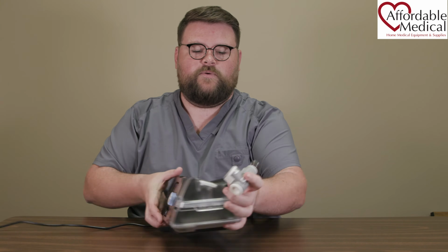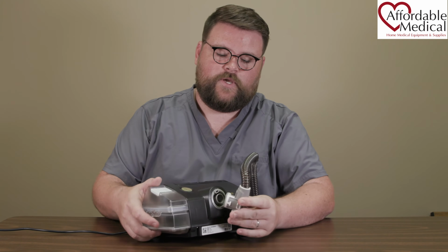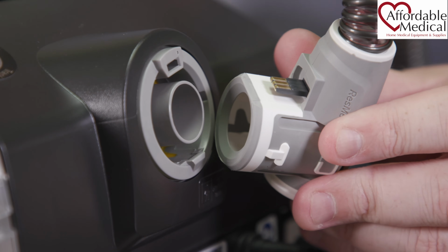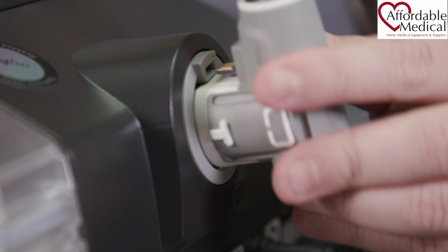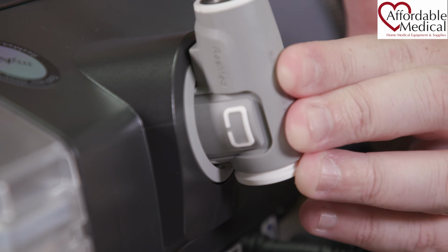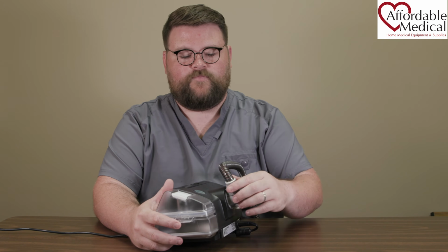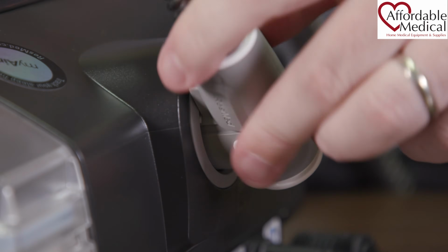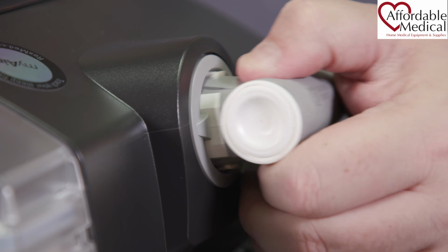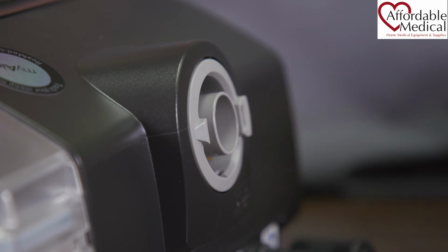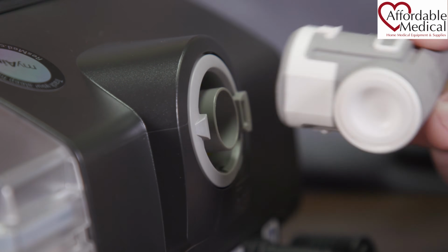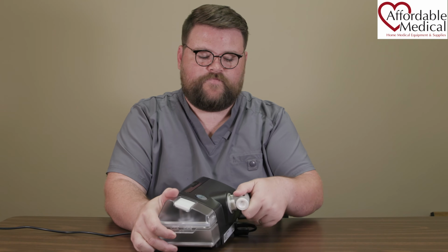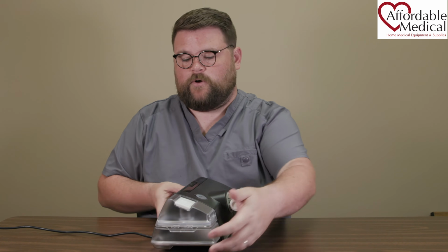Flipping the machine around, you'll notice the temperature probe connector there. We're going to line it up and you'll hear it snap, kind of like that. When you hear the click, you have it where it needs to be. You can swivel it to whatever side of the bed you need, and you just squeeze the tube to pull it out. Next time you'd plug it in whichever direction that connector needed again. Just push it in, listen for the snap, and you're good to go.